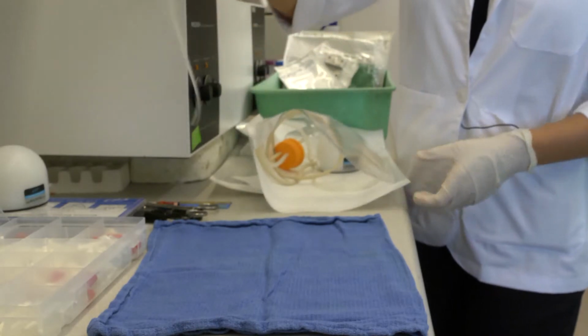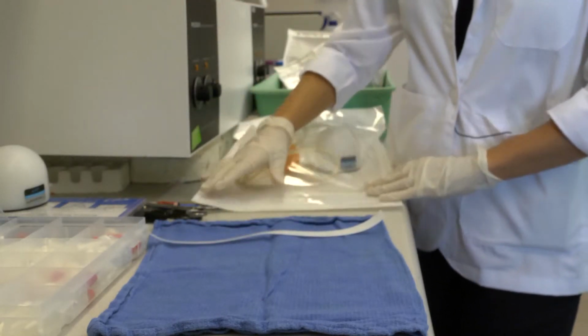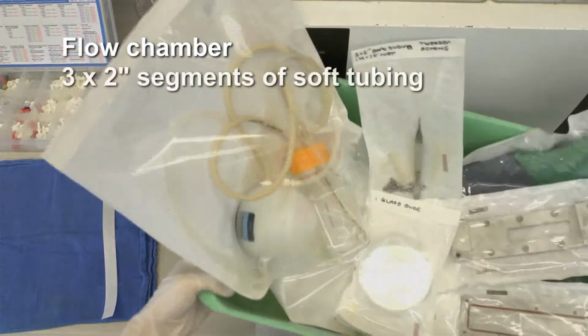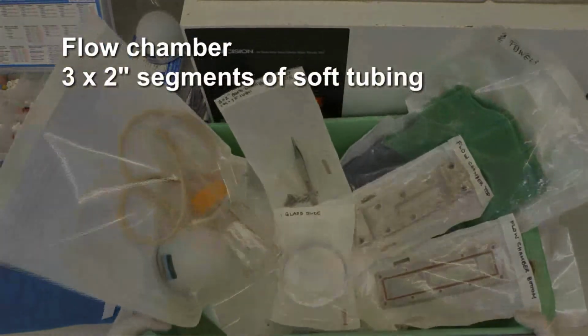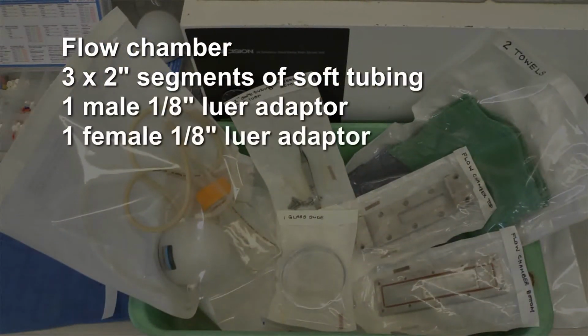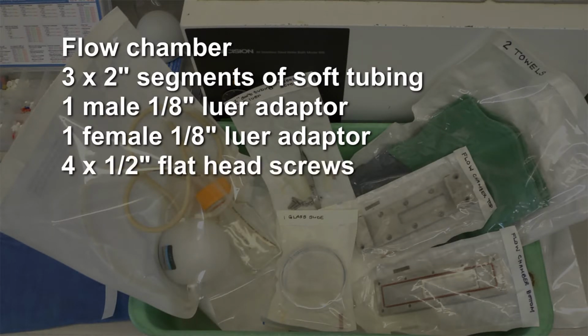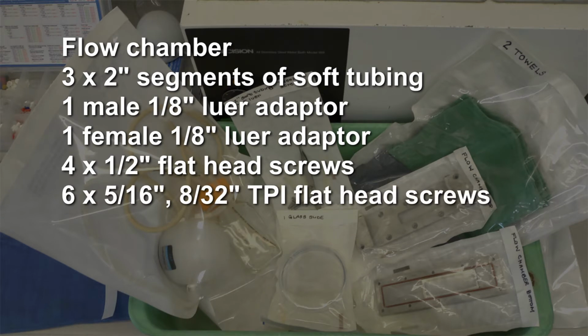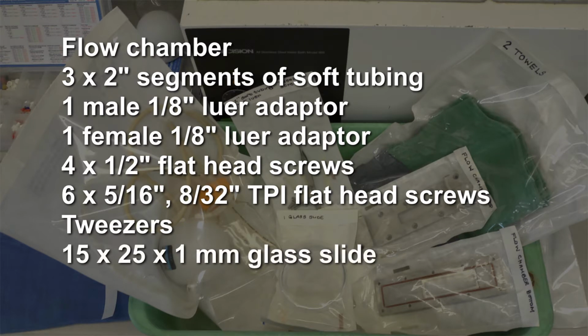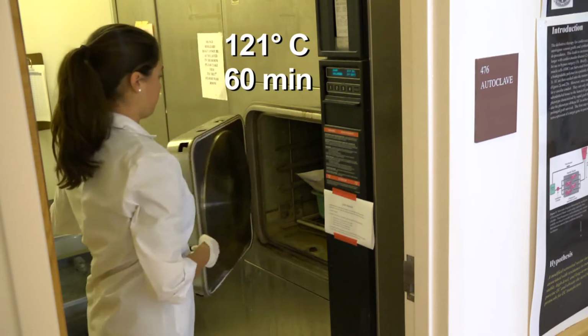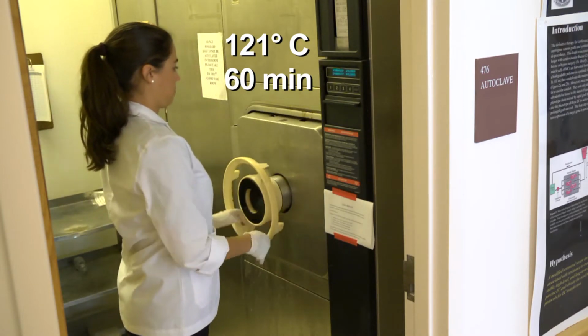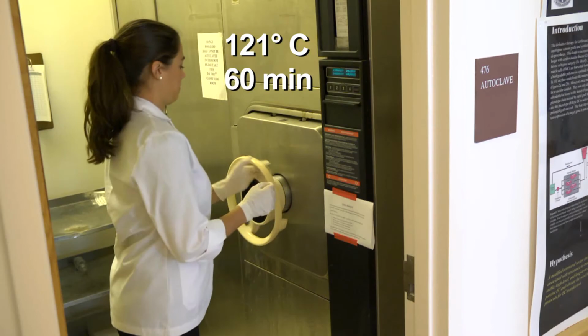In addition to the assembled parts, these parts must be sterilized: 1 complete flow chamber, 3 2-inch segments of soft tubing, 1 male and 1 female 1/8-inch Luer adapter, 4 1/2-inch flathead screws, 6 5/16-inch 8/32-inch threads per inch flathead screws, 1 pair of tweezers, 1 glass slide, and 2 towels. Sterilize by steam autoclaving at 121 degrees Celsius for 60 minutes.